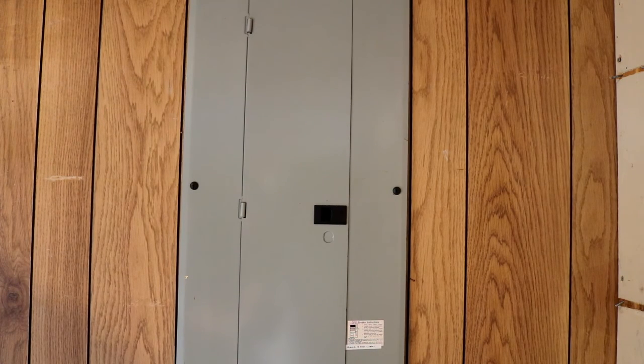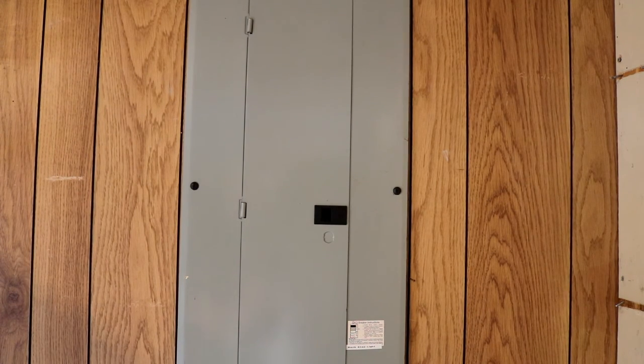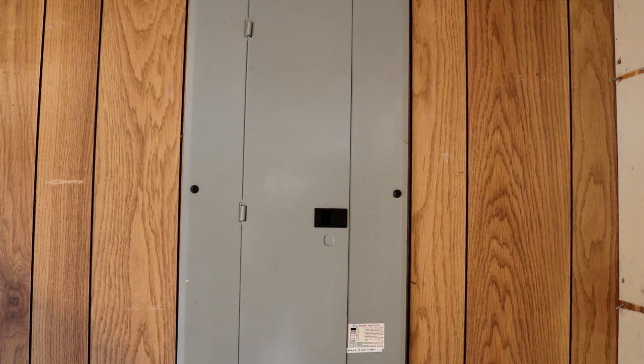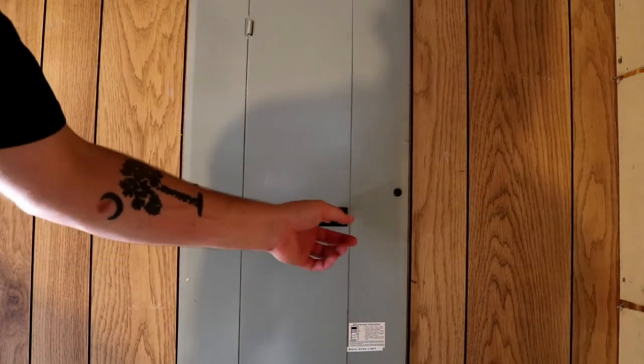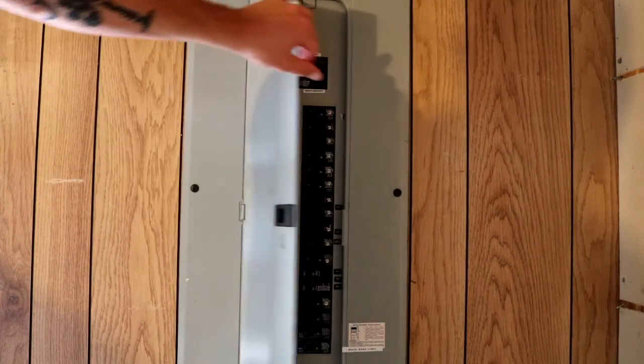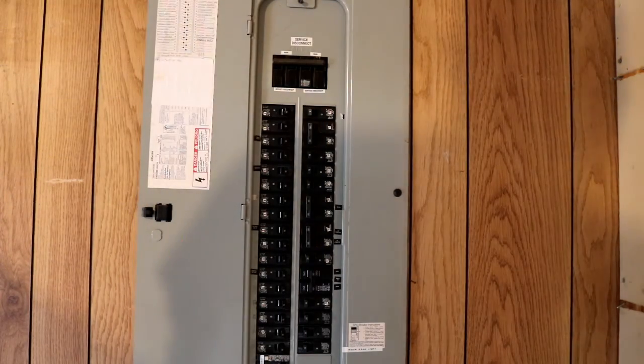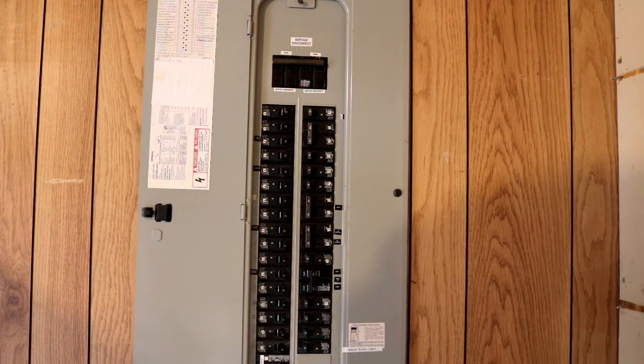Alright, here we are at the service panel. I showed you the meter outside, and I showed you the transformer, so we'll go step by step. It comes in from the transformer, goes straight down through the meter, and into this 200 amp service panel. Right out from that transformer, the electricity comes in here to my service panel.